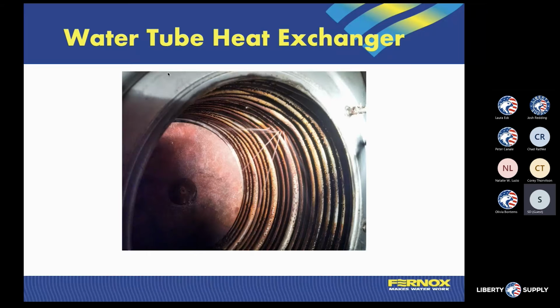This is a failure based upon the fact that there was water or fluid in the system that caked up or built up so badly in the system that the water could not be transferred anymore, and the burner overtook the metal from that standpoint.